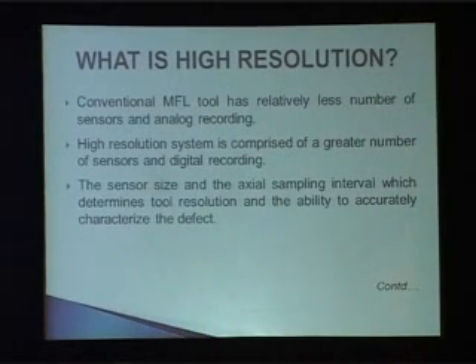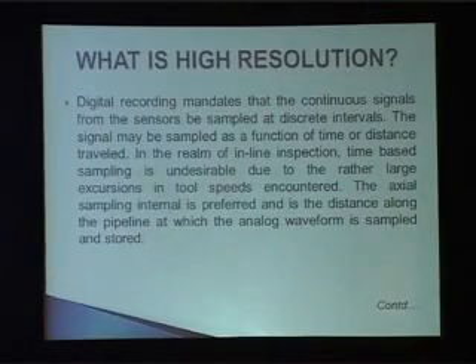The next important terminology in inline inspection is high resolution, because everybody must be knowing that we specify high resolution tool. Now, what is high resolution? Conventional MFL tool has relatively less number of sensors and analog recording. High resolution system is comprised of a greater number of sensors and digital recording. The sensor size and the axial sampling interval determine the tool resolution and the ability to accurately characterize the defect. That is basically the meaning of resolution. Means higher is the number of sensors, the more accurate result we shall get. There is something else on which resolution depends.